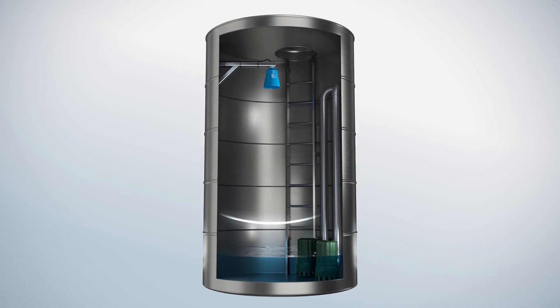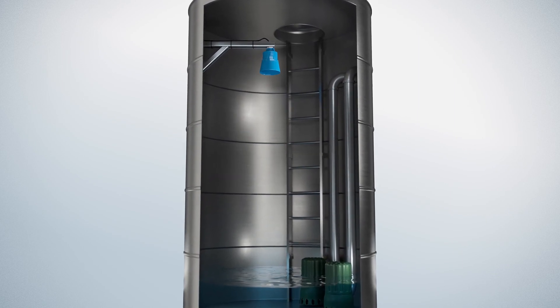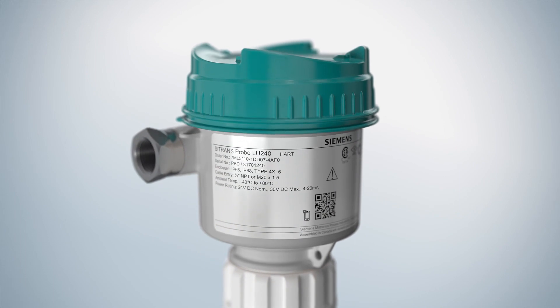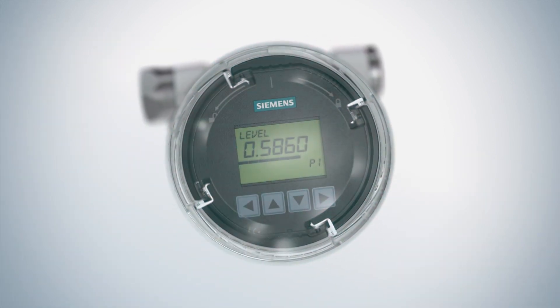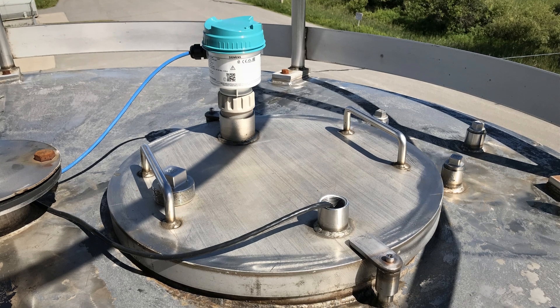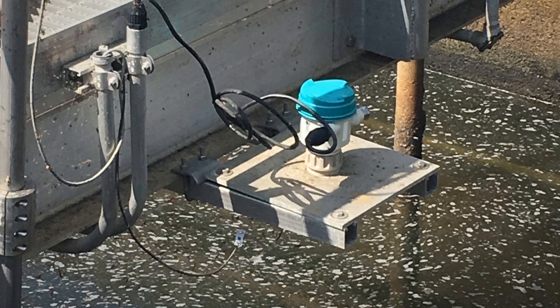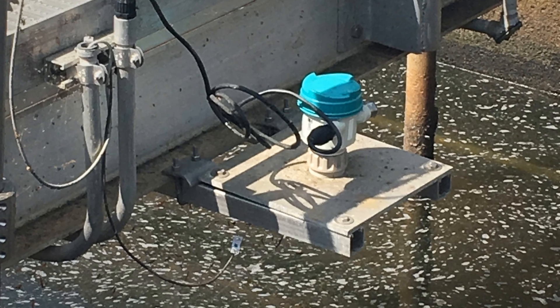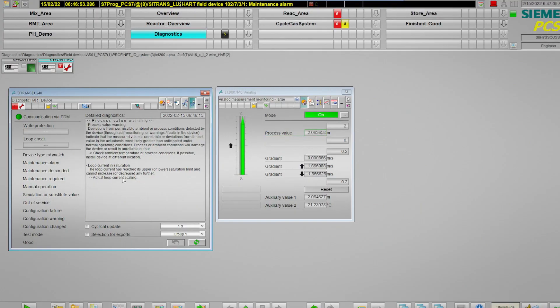In this example, we are troubleshooting a maintenance alarm from one of our level transmitters. The SITRANS LU240 level transmitter uses ultrasonic technology and is endowed with process intelligence for both simple and challenging level applications across all industries, as well as dynamic adaptability to changing process conditions using advanced algorithms. The diagnostics message indicates the maintenance alarm is from a loss of echo, which could be due to factors like excessive moisture buildup, material being too close to the transducer, vibrations, nozzle height, or that this unit simply needs to be replaced.